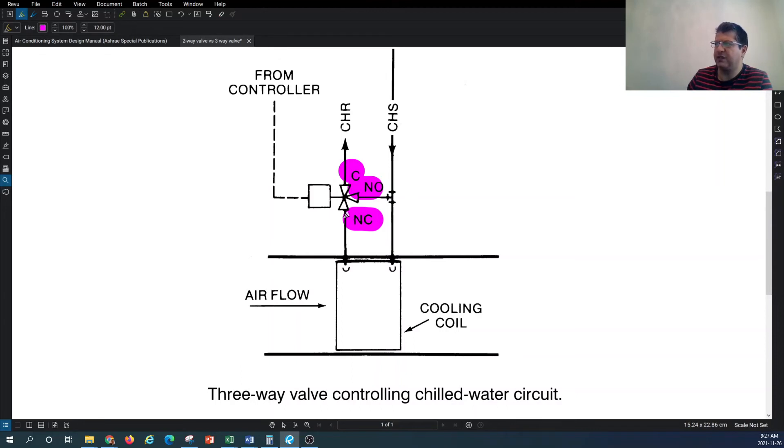If your return side valve is 100 percent open, it means you want the entire flow designed for that coil to circulate through that coil. This means your diverting side of the three-way valve will be fully closed and there is no flow coming there. So 100 percent goes into the coil, 100 percent comes out. You can modulate that. This is in response to the constant flow type of heating or hydronic loop where you don't have modulation on the hydronic fluid as a whole in your entire loop, but you want to have modulation locally into the heating or cooling coil in this space.